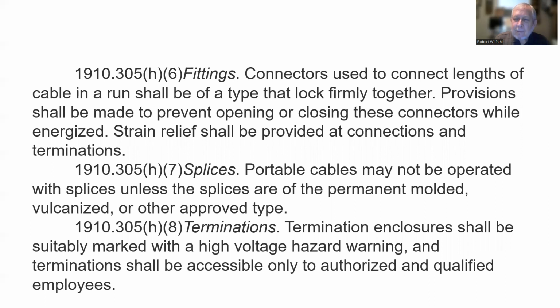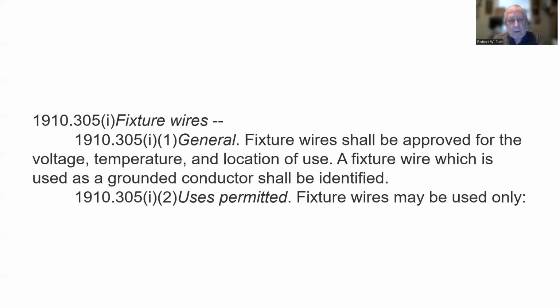Now, can you cut a cord and splice it? No, not splice it. But if you've got a 100-foot cord with a piece of insulation messed up in the middle, you can cut it and make two 49-foot cords, as long as you put an approved plug on each end. Then you have an extension cord that doesn't have any breaks in the insulation, and that's fine. But extension cords are something to look out for as a safety professional.